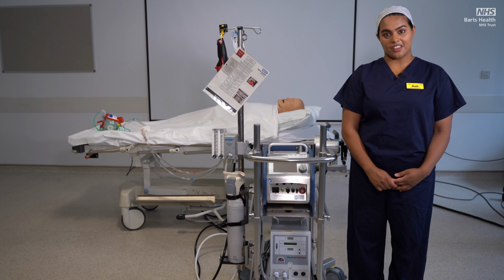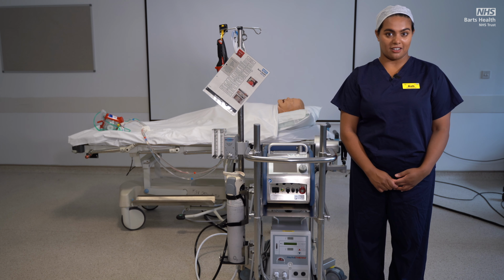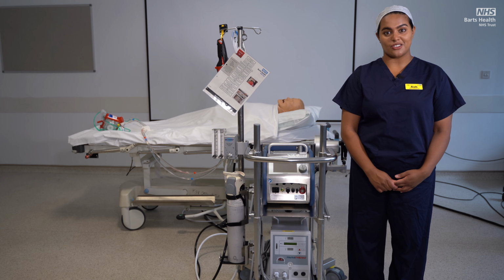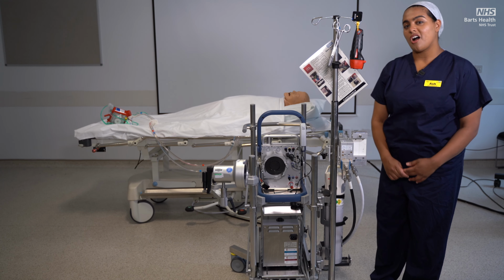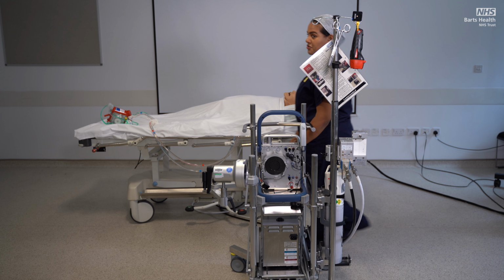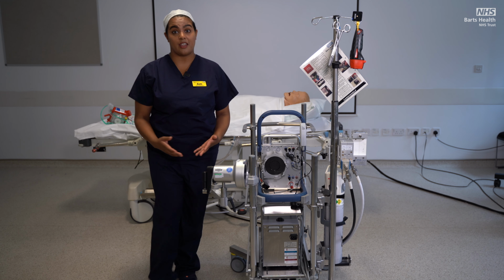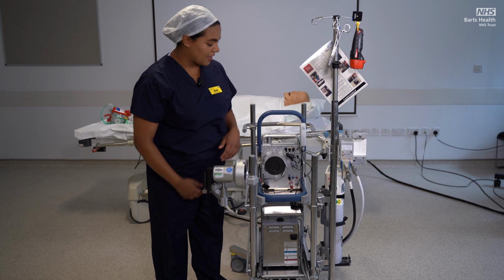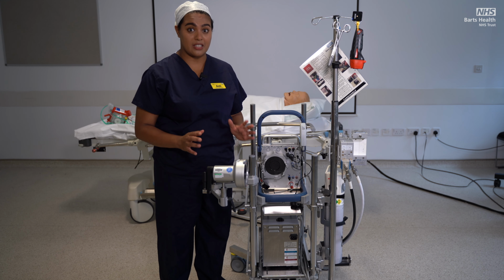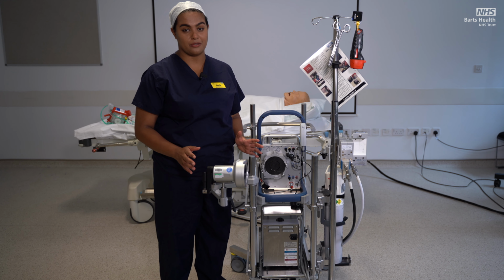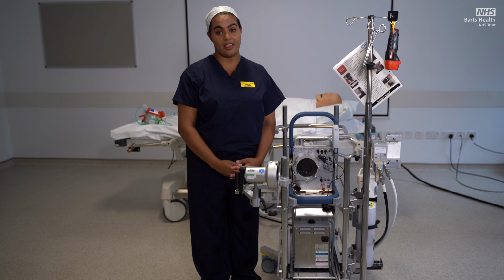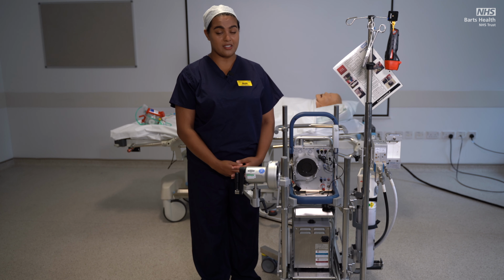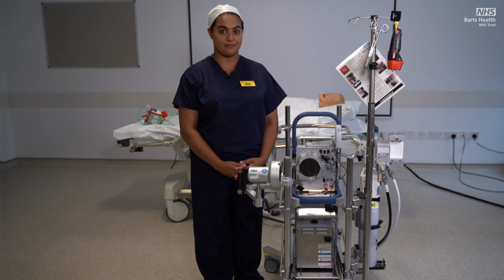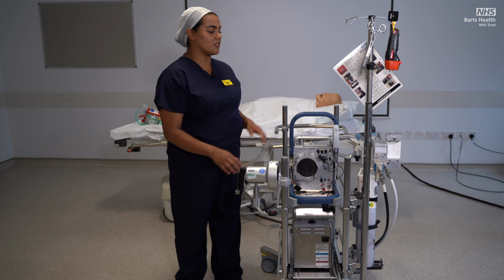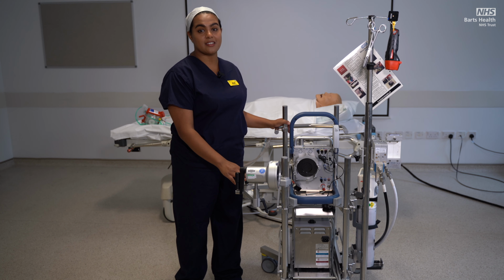On the reverse side of the Cardiohelp is the monitoring plug-in panel, where the ECMO pump and oxygenator will be located. All of the patient and console monitoring arise from the plug-in monitoring part of the console, and at no point during the ECMO run should these be directly detached from the console. Any problems relating to the console or hardware or the circuit should be escalated to the on-call perfusionist via the Barts switchboard. The Cardiohelp console is located on its own transportation trolley known as the Sprinter cart.